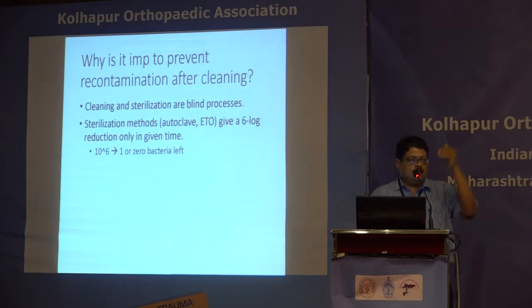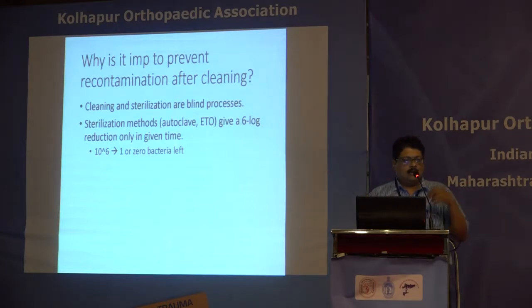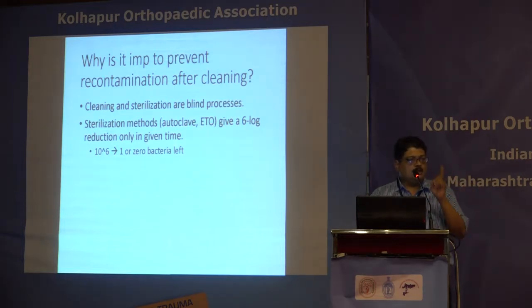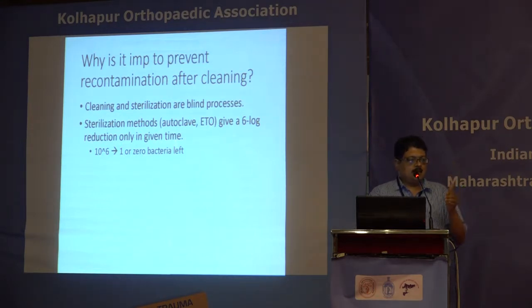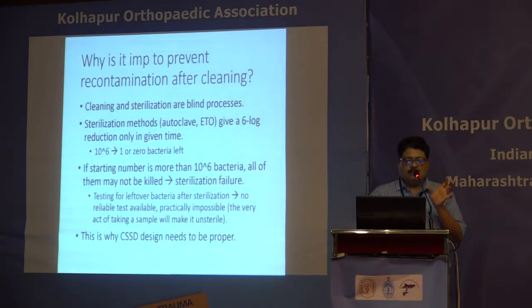Every time you use a sterilization method it gives the same log reduction. So if you start out with 10^20 organisms, the machine will operate correctly and sterilization indicators will pass, but you will only get a 10^6 log reduction — not a 10^20 reduction — so something can remain back. This is why it is so important to prevent recontamination after cleaning, and that is the most important basis for CSSD design.